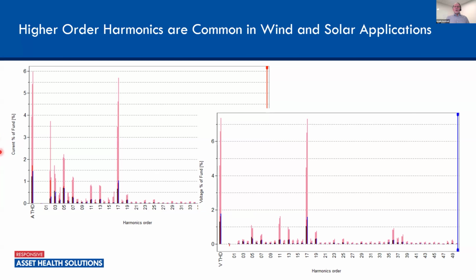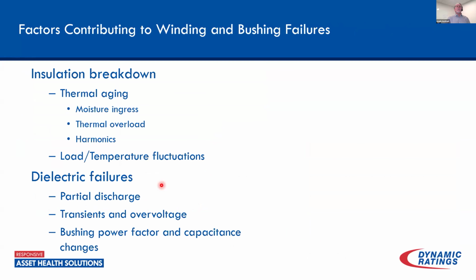That was the current distortion here. Here's the voltage distortion. And again, we talked about that earlier. We're seeing values exceeding 7%. So in addition to that insulation breakdown that we're worried about when it comes to renewables, we're also concerned about dielectric failures. And this is the area where we often get questions from customers because they're seeing increased DGA values. In particular, they're seeing high levels of hydrogen. And typically those are being associated with partial discharges within the transformer.